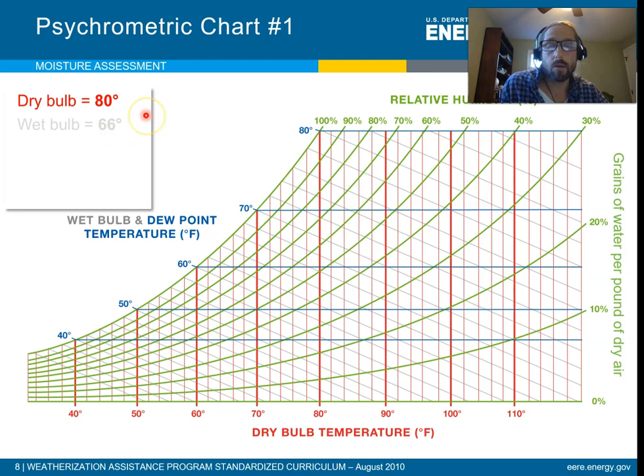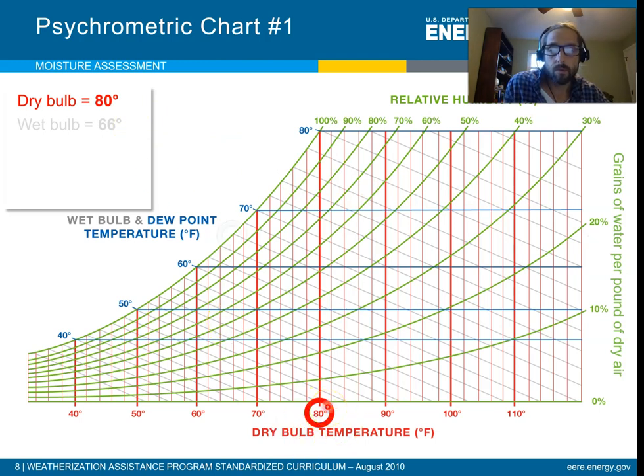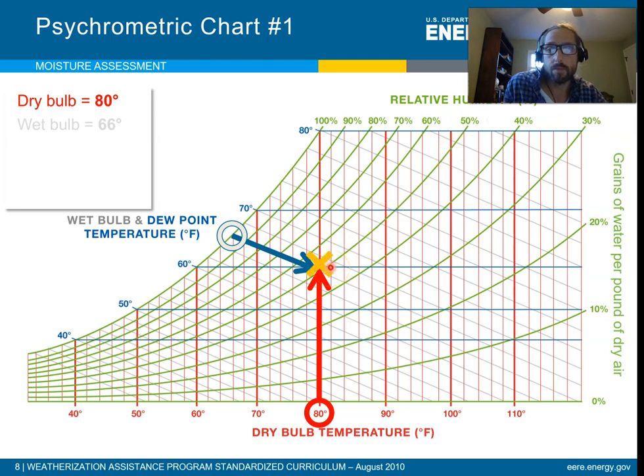Let's say we do our sling psychrometer and get a dry bulb of 80 and a wet bulb of 66. On the psychrometric chart we have dry bulb here, wet bulb and dew point, and the relative humidity shown by these green curved lines. Over here is our grains of water vapor per pound of dry air — our absolute humidity. So we find 80 on the dry bulb, go up, find 66 on the wet bulb line, and find where they meet, which falls almost exactly on the 50% relative humidity line.